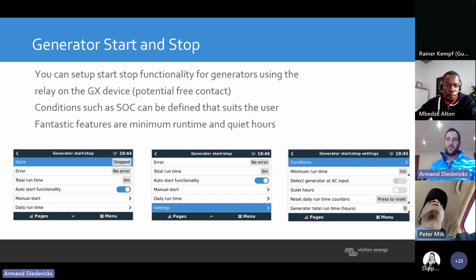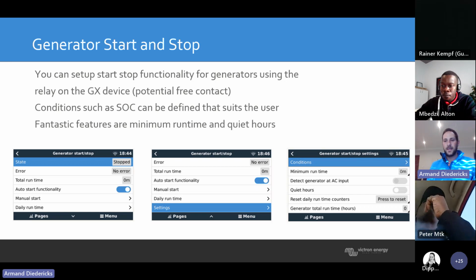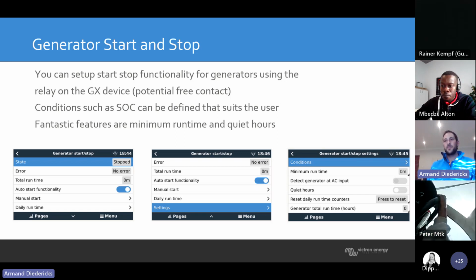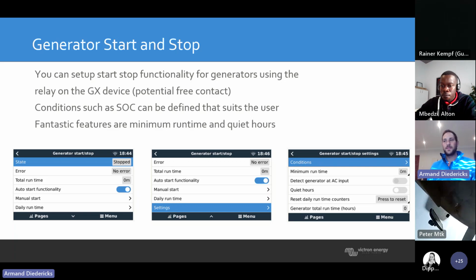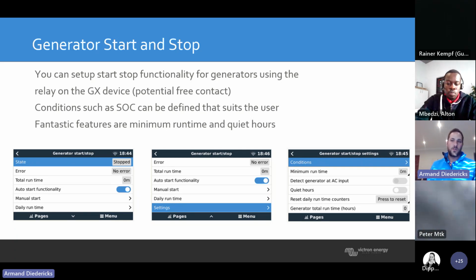So runtime: it's ideal for a generator not to stand without running. You need to have a cycle on the generator and run it at least once every 2 weeks for at least 5 to 10 minutes, just to get the circulation into the generator. You can actually set it onto the auto start functionality, or manually start at a certain time, or a daily run time, and say, okay, start at this every 2 weeks or every couple of hours.